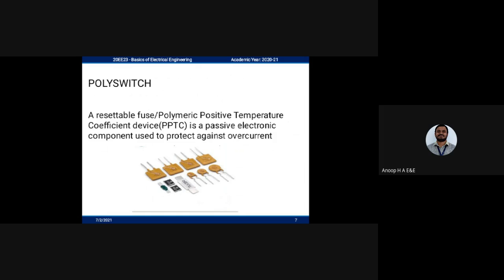The poly switch is a device in series with elements in a circuit that responds to an overcurrent condition. The device increases in resistance, reducing the current in the circuit to a value that can be safely carried by any of the circuit elements. And the next one is the earthing. The process of transferring the immediate discharge of the electrical energy directly to the earth with the help of a low resistance wire is known as earthing. The function of earthing is to protect us from an electrical shock and to cause protective devices to switch off the electrical current to the circuit that has a fault.